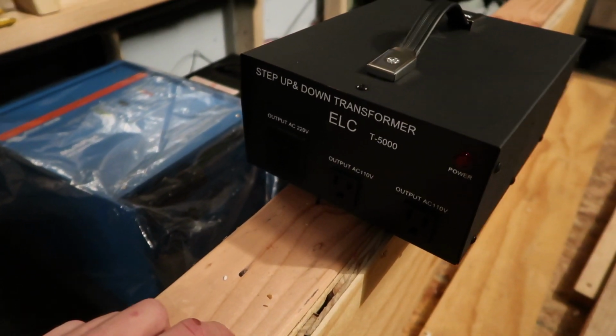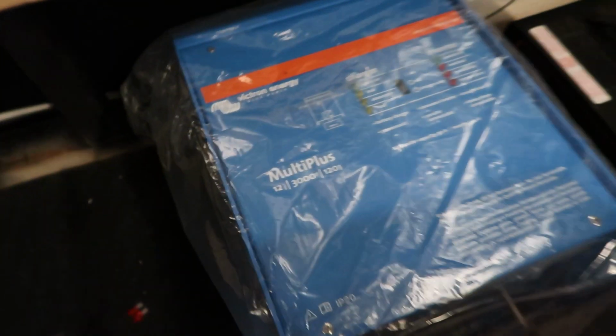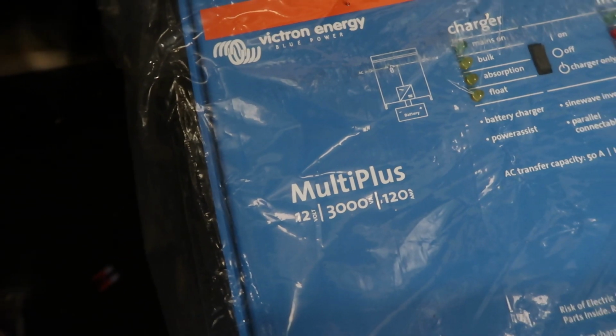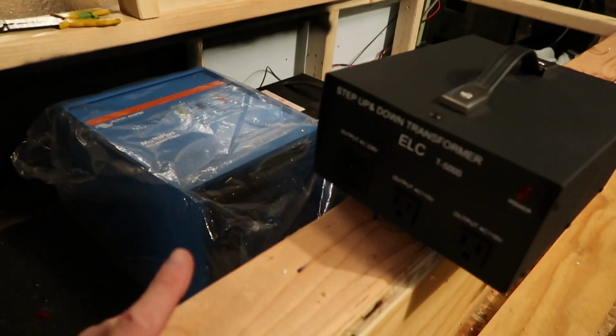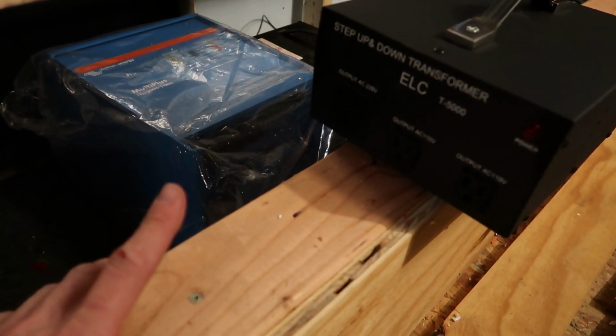One other hurdle I came across when building this unit is that all of the ducted mini split units run off of 240, not 120, and the inverter I have puts out 120, not 240. So after doing some extra research, I found online that they make a step up or step down transformer, and I needed a step up transformer to go from 120 to 240 to run the system.